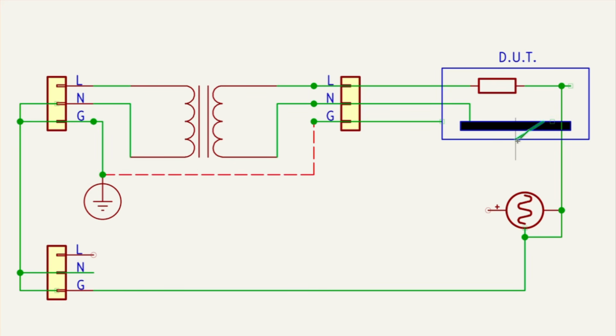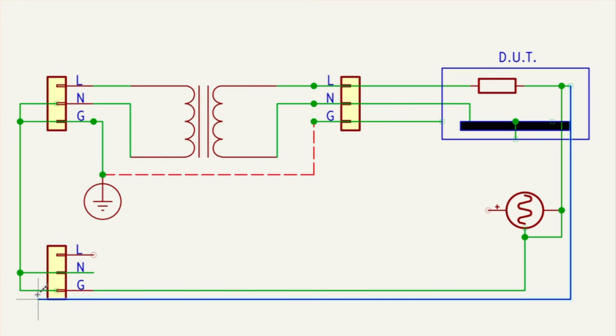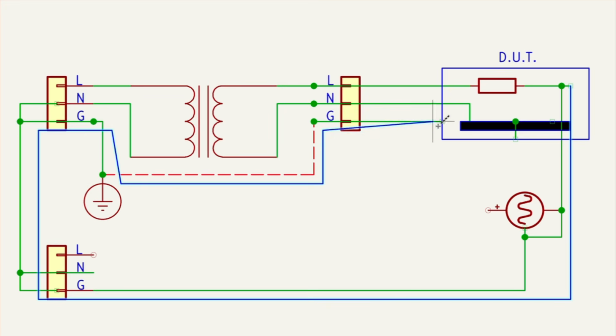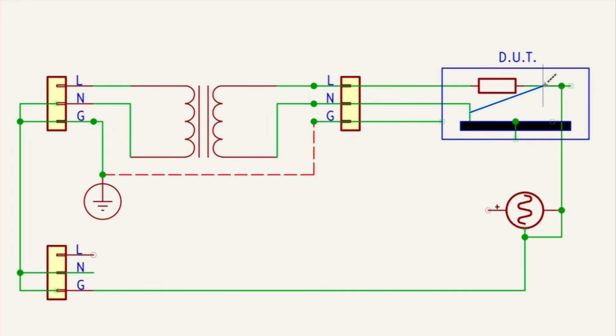Now if this happened to be connected to the chassis, let's say the ground plane of this device is connected to the chassis like that, what happens if I connect the ground of my probe to a high voltage point? Now we have an issue — a closed loop. The path is fully open, and connecting through the chassis, I come to my ground and essentially short to the neutral of my mains. That's shorting these two together, which causes a big bang, huge surge current, lots of damage probably. So we don't want that.